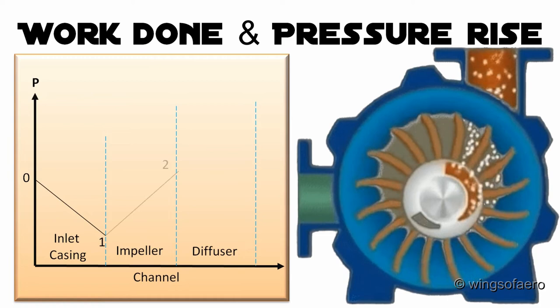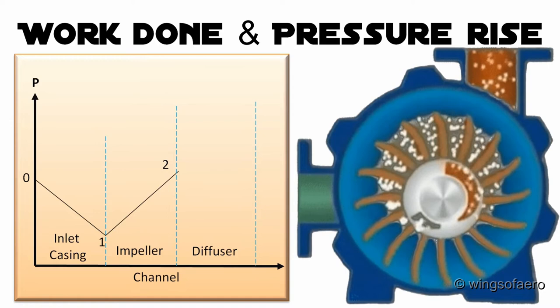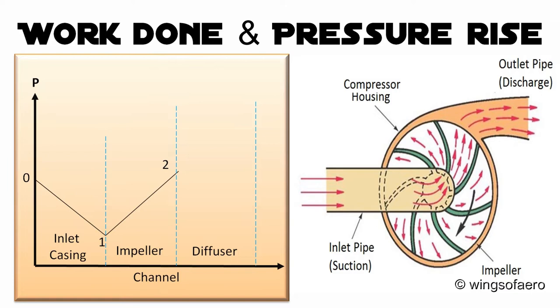Energy transfer takes place in the impeller, and the static pressure of the air increases from the inducer to the impeller tip due to centrifugal acceleration. The purpose of the diffuser, whether vaned or vaneless, is to convert the high velocity of the air leaving the impeller into pressure by slowing it down carefully to an acceptable level.